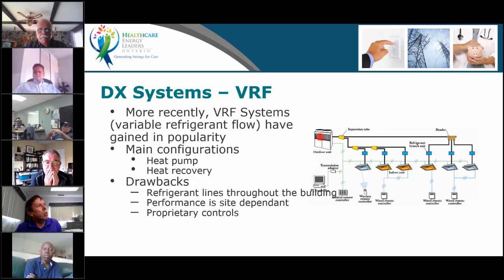And what you have in those lines is refrigerant going in and circulating all over the building. They are efficient, but they can lose efficiency quickly if they have very long service lines. So if it's very long to get to the outdoor unit, to the indoor unit, the performance drops. And then you also have to think that you'll have refrigerant running all over your building and all of those lines. That's why some places really don't like to have VRF installed because of the number of refrigerant lines. They actually had to modify the mechanical code to allow some of those systems because they would have too much refrigerant and the space they were serving would have become mechanical rooms. So they would have to have exhaust and sensors, but the code was modified for that.